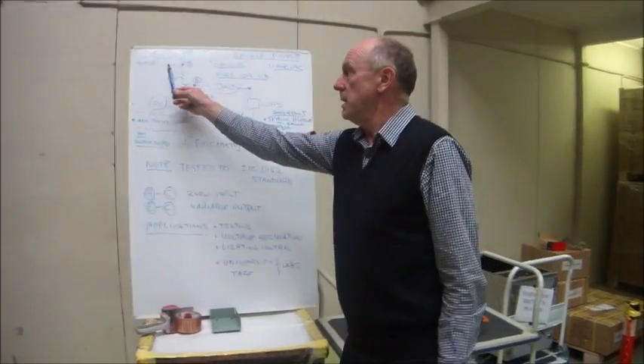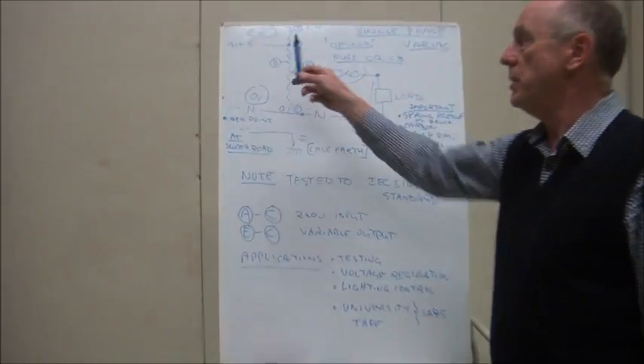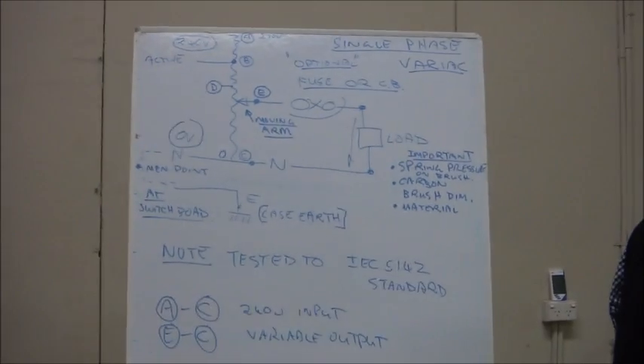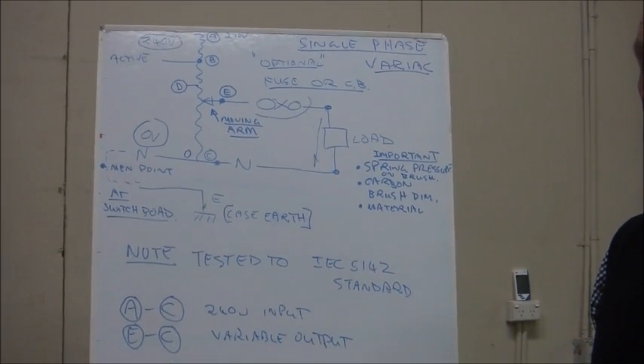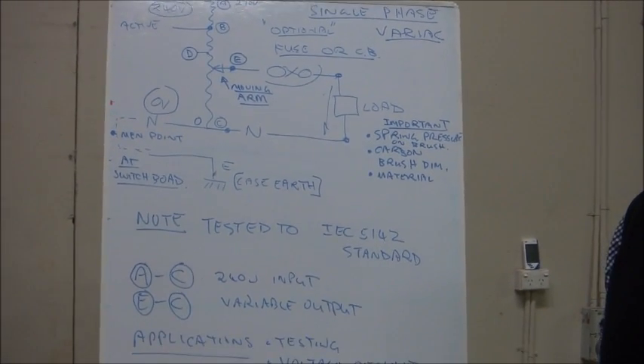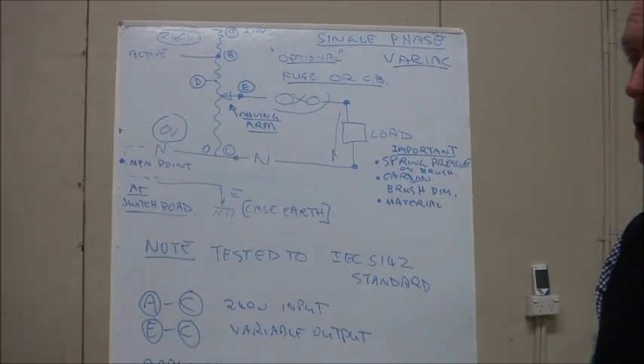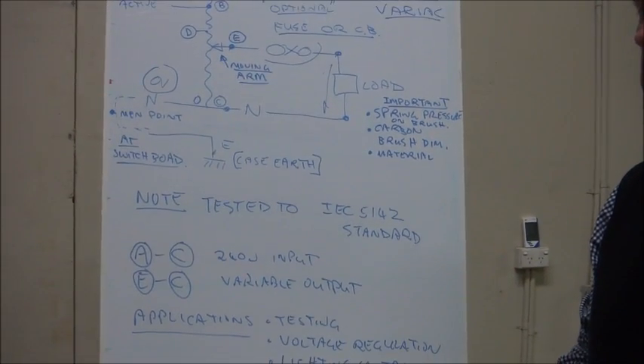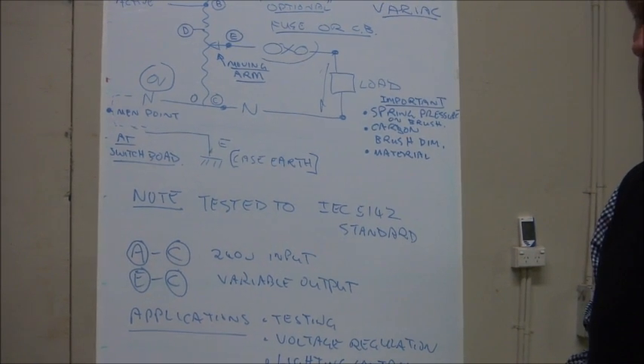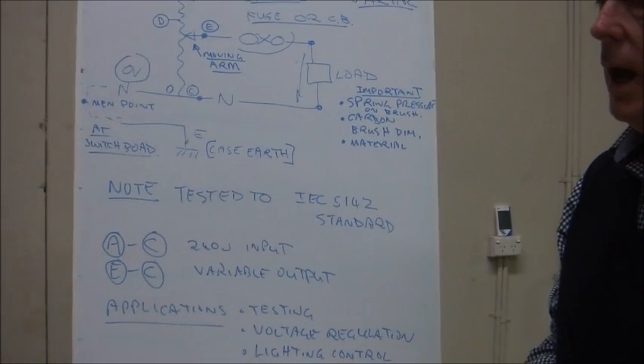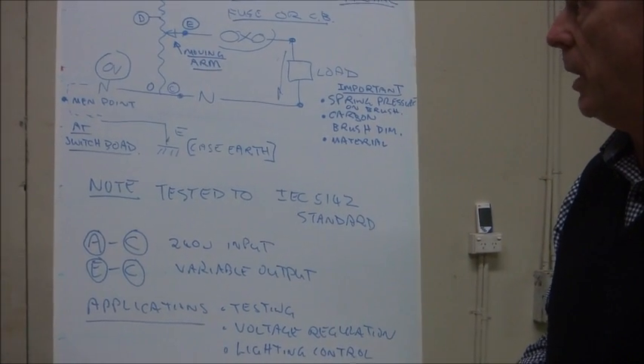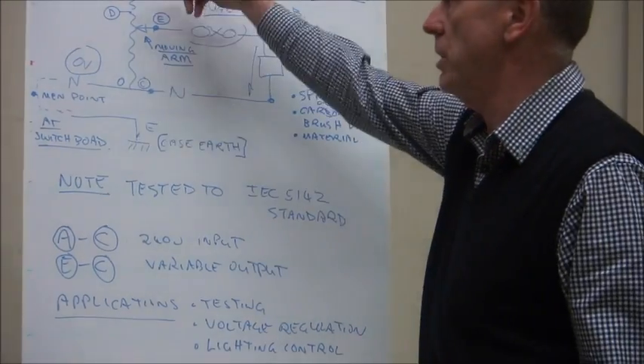The variac doesn't have isolation input to output, so you have to be very careful with it because there's no protection input to output. In other words, if you touch that terminal there and it's at high voltage, you can get electric shock. So it's only to be used by people that are technicians or electricians or people that understand what an auto transformer is, because this is just an auto transformer.